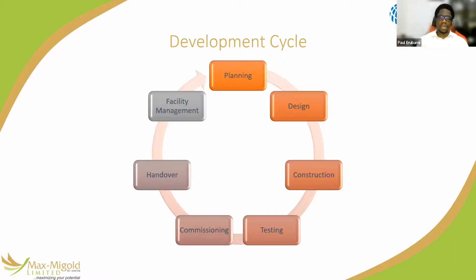The next phase is to test that things work. Testing is just for functionality: does the generator work, does it come on, does it bring up power? If a generator rated 1000 kVA can even power up one flat in the estate, at least it's working. But what about the temperature? Is it overheating? What about vibration, sound level, emission? You test for all of those.